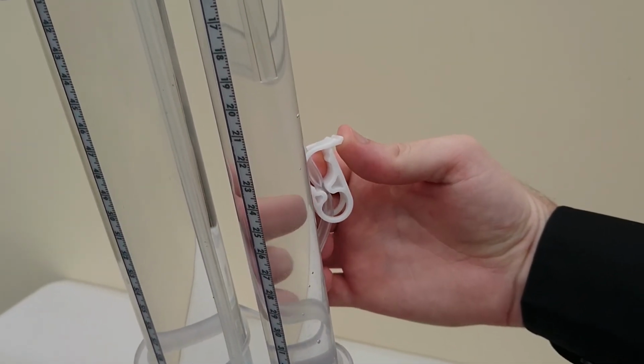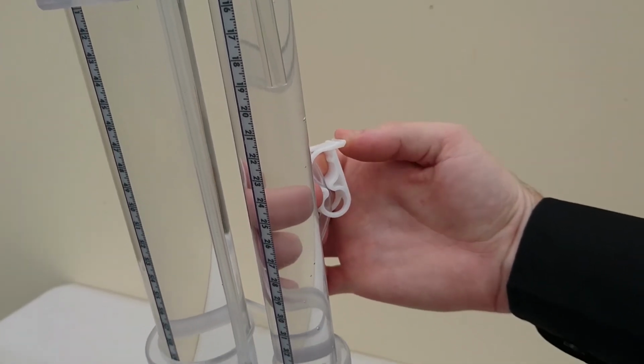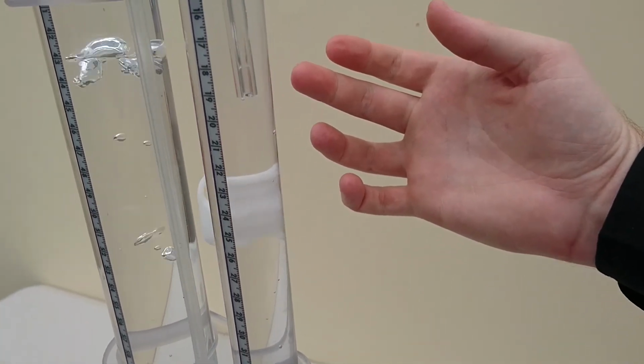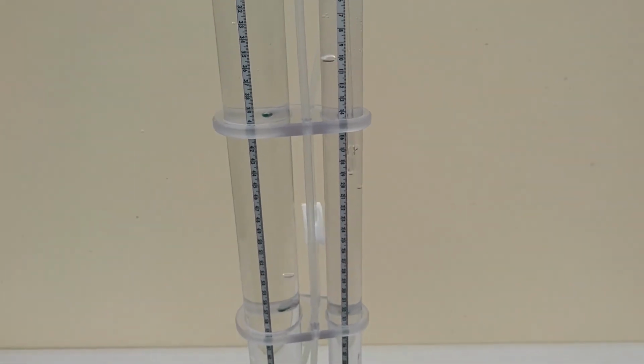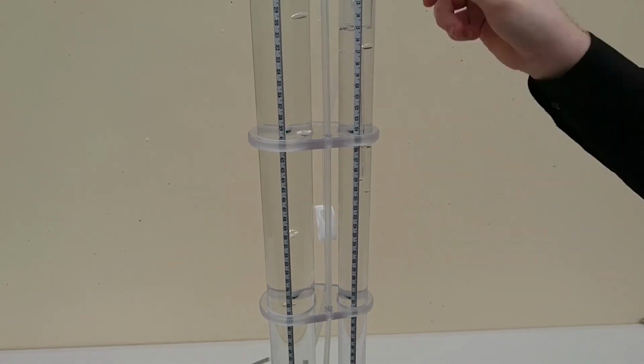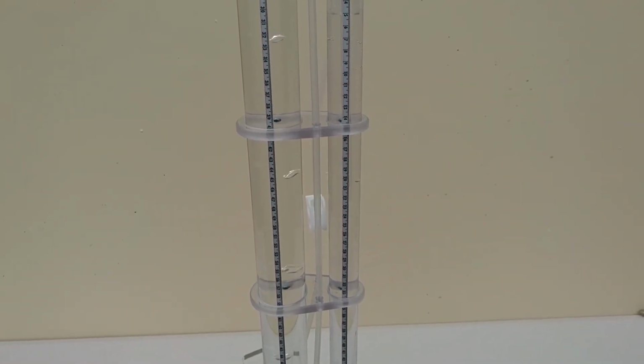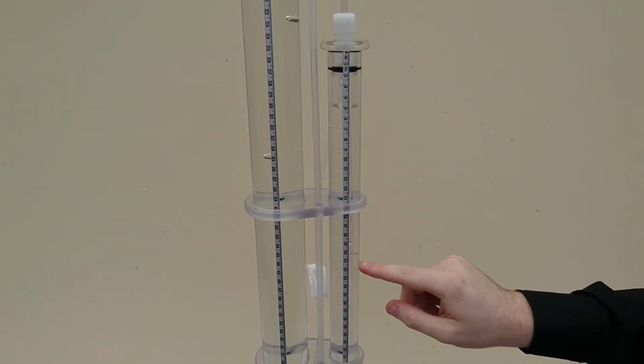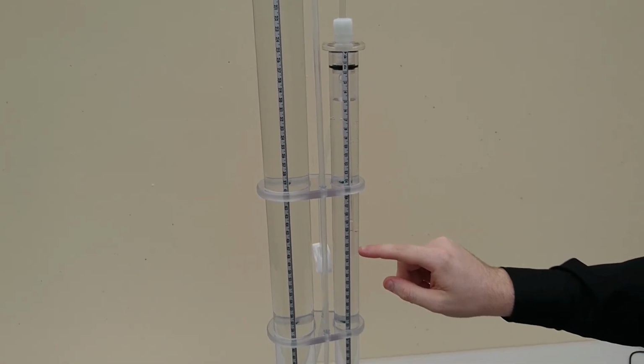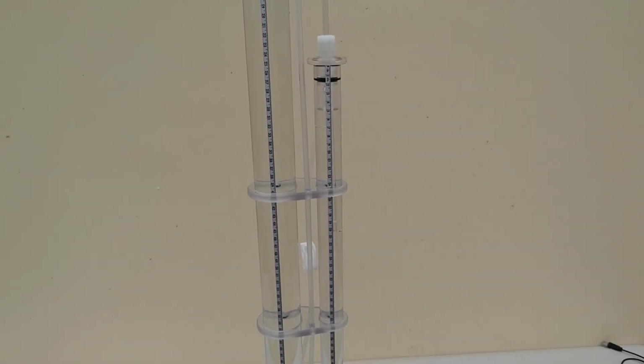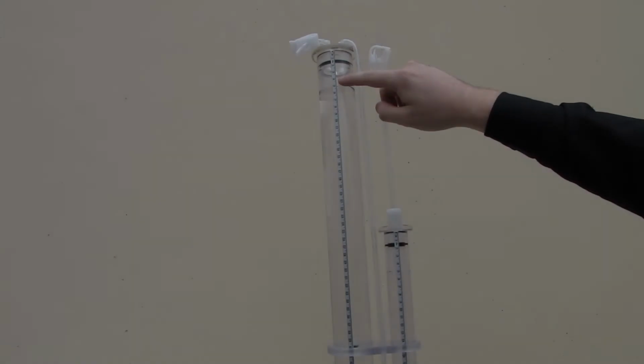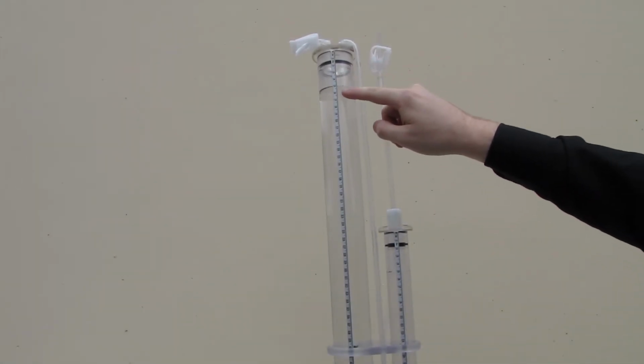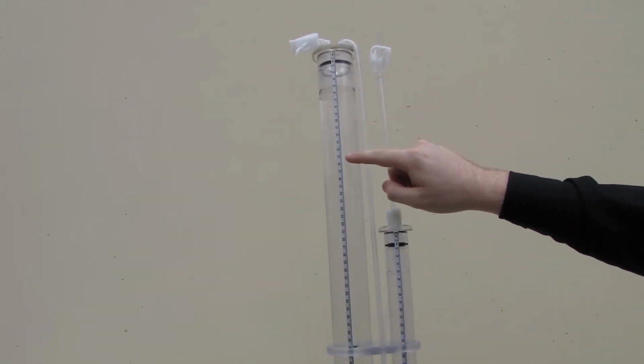Next, open the clip valve leading from the top hose of the bubble tower to the bottom hose of the water tower to allow air to flow. If bubbles flow in the bubble tower quickly, insert the bubble tower inlet tube further to stop the flow of air, shown here. You will notice that the level in the water tower will drop a slight amount due to the purging of air from the bubble tower to the water tower. This is normal.